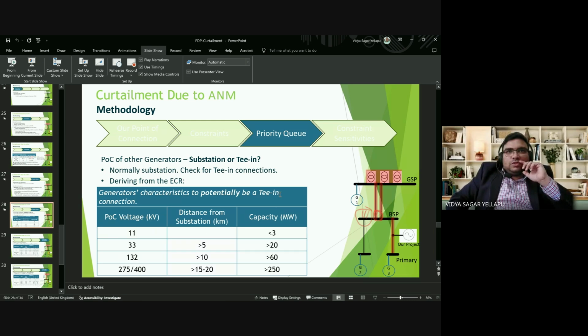This is to know whether a substation is teed in or not. That is based on the distance from the substation and capacity. If the POC, the point of connection, voltage is 11 kV and the capacity is less than 3 megawatts, then definitely that is to be teed in. If it is 33 kV, then if the distance from the substation is greater than 5 km or the capacity is greater than 20 megawatts, then it is to be teed in. That kind of rules are there that need to be understood.